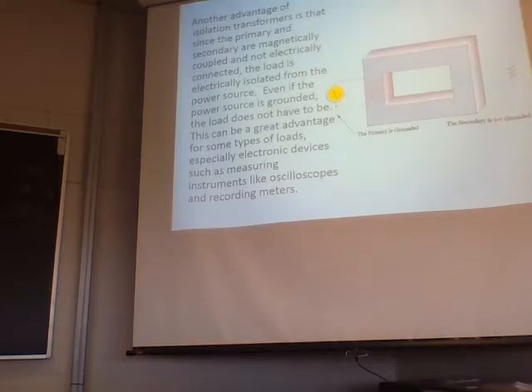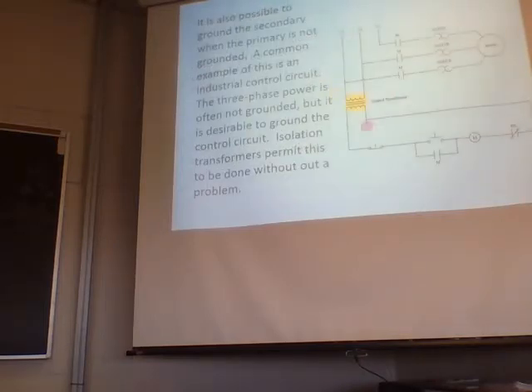It's also possible to ground the secondary when the primary is not grounded. A common example of this is an industrial control circuit. Three-phase power is often not grounded. So here you've got line 1, line 2, line 3. But it's desirable to ground the control circuit. So if this is 600 volts line to line, a 600 volt motor, you take line 1, line 2 to a single phase transformer, and on the secondary, because of the number of turns, you've got, say, a 120 volt control circuit. And when you've got 120 volts, you want to ground that neutral. So you can ground it over here for your control circuit.